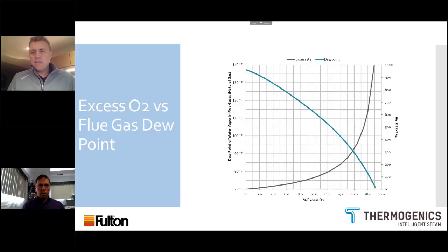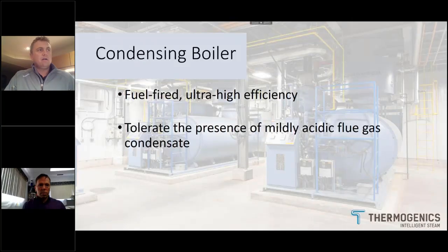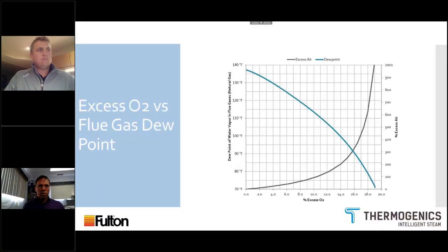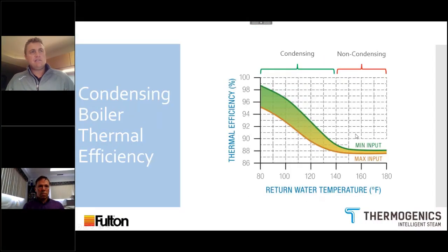Condensing boilers in particular are usually multi-unit cascading systems operated in parallel at their lowest firing rates, which is good. That's where you're going to achieve these high changes in terms of turn down. I'm just going to go back right here. So there you go. There's what we were talking about, how you want to get back into those lower temperatures.